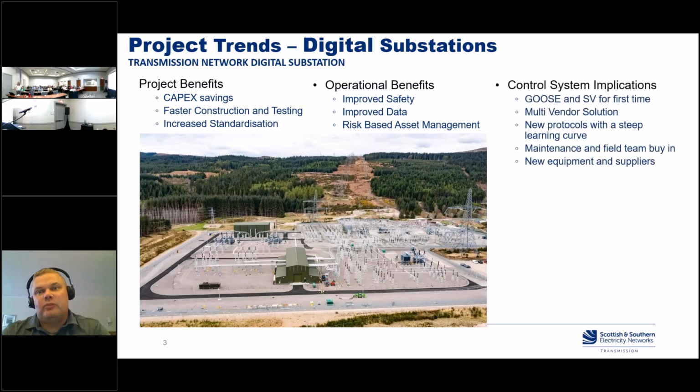The most interesting aspect for me is obviously the control system implications. We're deploying GOOSE and sampled values for the first time, using multi-vendor solutions for publishing and subscribing. These again were new protocols for us with a steep learning curve. We thought we'd done a lot of learning in the last 10 years with station bus and MMS, but once you scratch the surface of GOOSE and sampled values, it obviously multiplies up even more, and there's so much more to know underneath there.